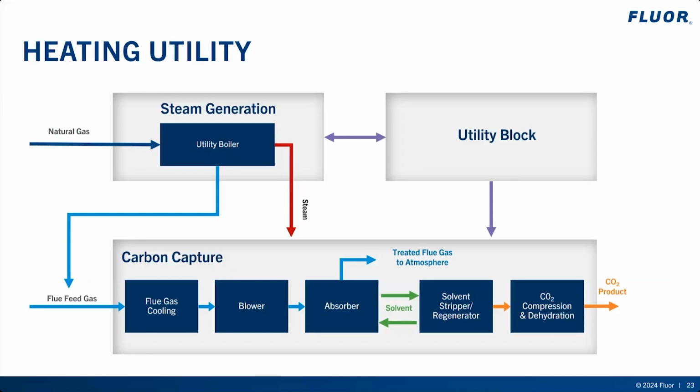This results in a compounding effect on the size of the system as additional emissions result in additional steam demand. A base case utility boiler design will typically converge on a design that is roughly 20% larger to maintain the desired reduction in carbon intensity of the overall facility.